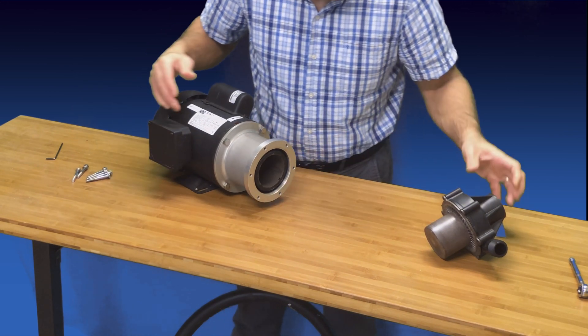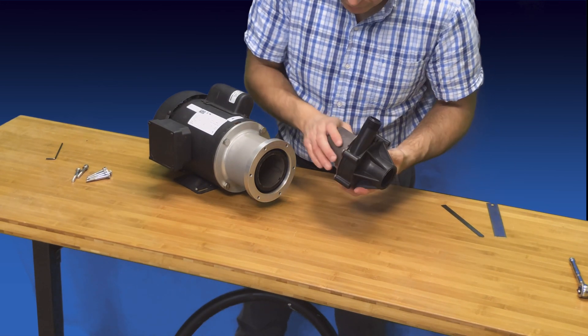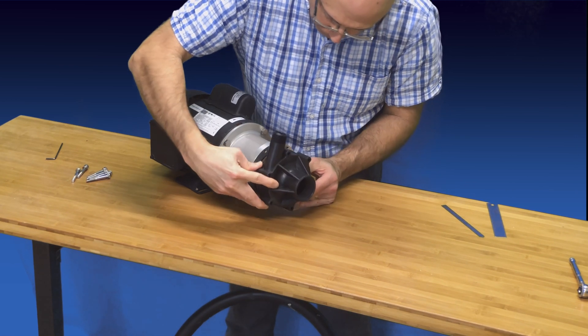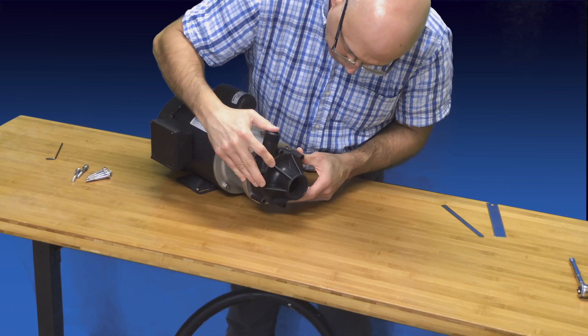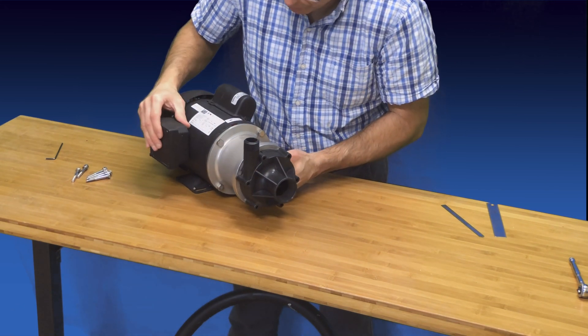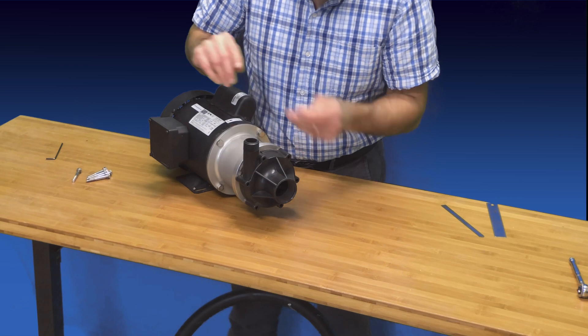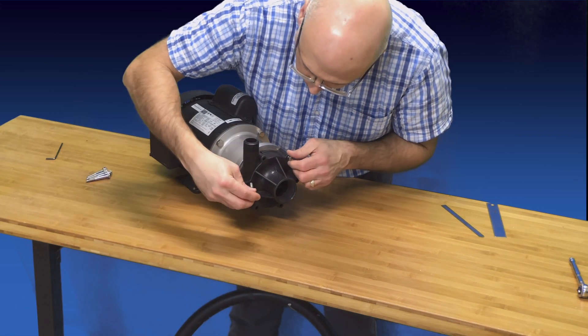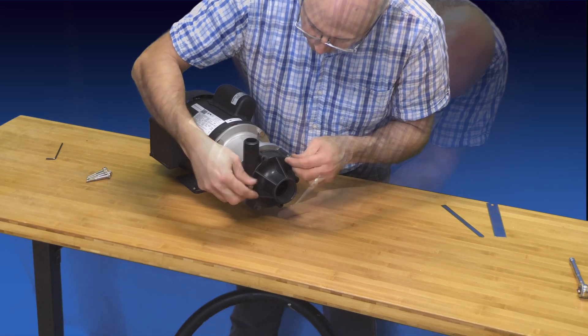Next, take the previously assembled wet end assembly and slip it into the just assembled power end assembly. Hold these two assemblies firmly in your grip as you bring them together, as the magnet forces will pull on them strongly. Align the bolt holes on these two assemblies, then install the screws to hold them together. Tighten all the screws with a wrench.